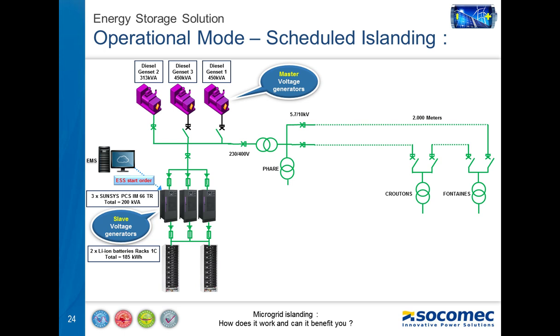From the initial state, when the local renewable generation is significant, the energy management software, which has been designed in this precise project by EDF Store and Forecast, can make the decision to start the storage system for two reasons. The first one, to ensure the microgrid voltage and frequency stability in case of instantaneous PV deviation, by making the storage work as a slave generator in parallel with the genset. So in this case, the energy storage system will just follow some P and Q set points coming from the energy management system. The second situation is when the local production is higher than the local consumption. The storage system is started and the genset can be stopped in order to make fuel savings. In this case, the energy storage system will ensure the grid forming and the responsibility of the frequency and voltage quality and stability.